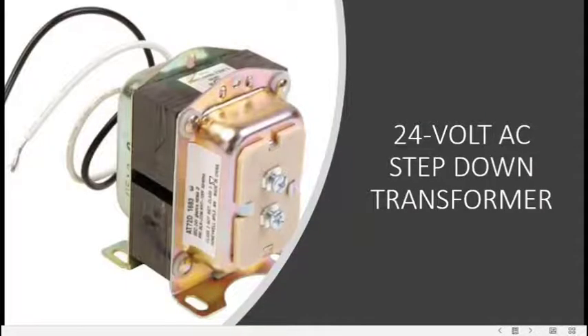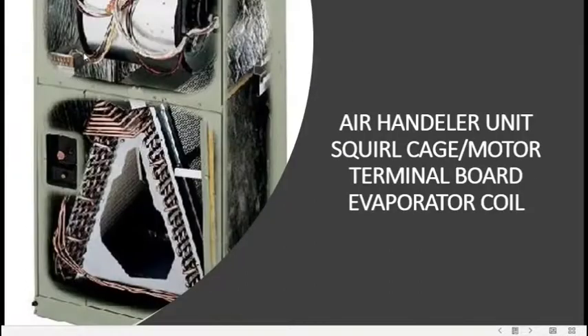This is your typical step-down transformer. This one, I believe, is 120 volt to 24 volts on this side. Your 120 or 220 volts is wired up on this side, and it steps down the voltage to 24 volts AC. And you would put your red and your white wires on there going to your air handler unit. Your 24 volts would come off of your air handling unit. And if you have 220 volts coming to your air handling unit and you don't have any voltage from your 24 volt, then your transformer, or you might have a fuse bad in your transformer. You might want to check that out.